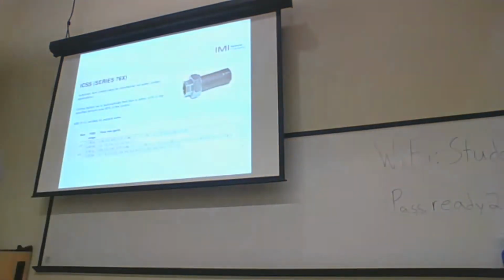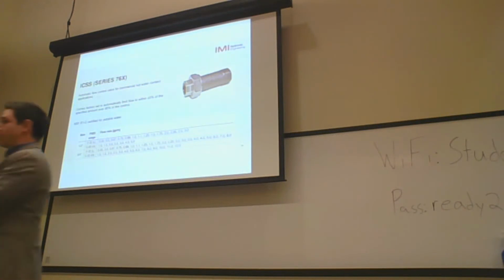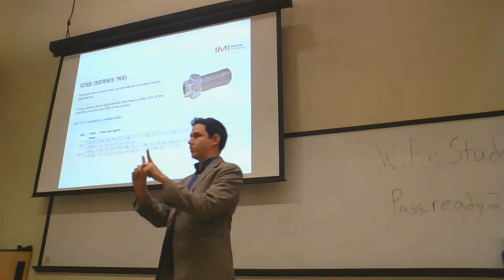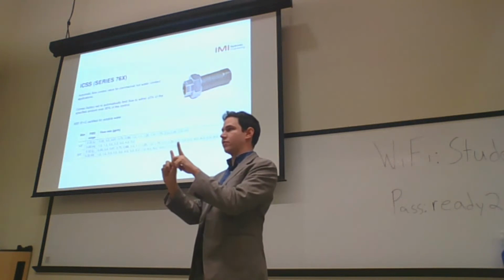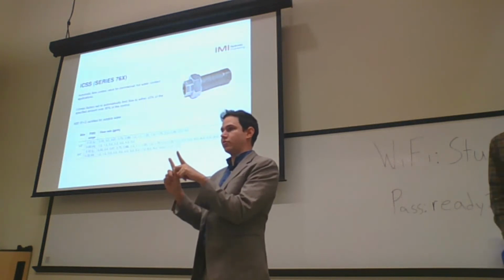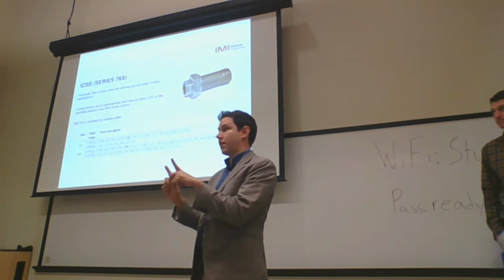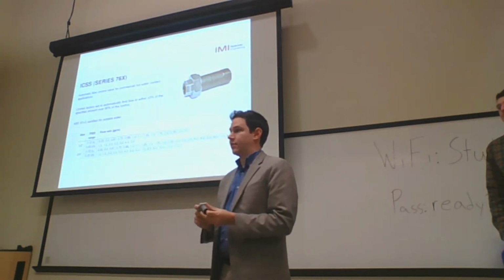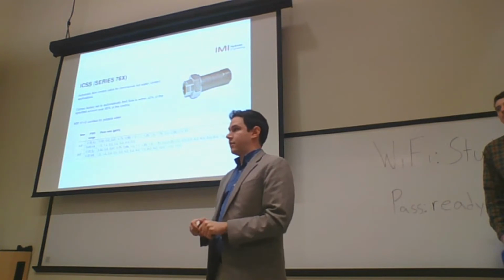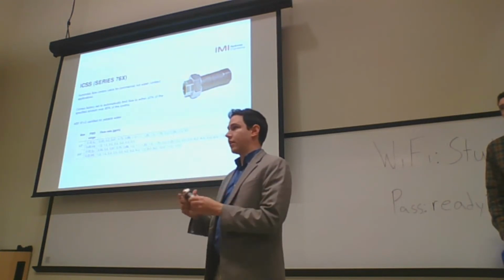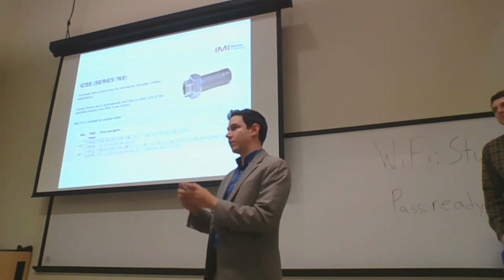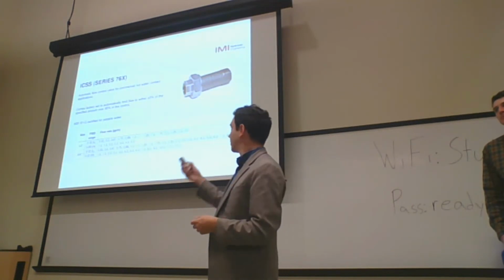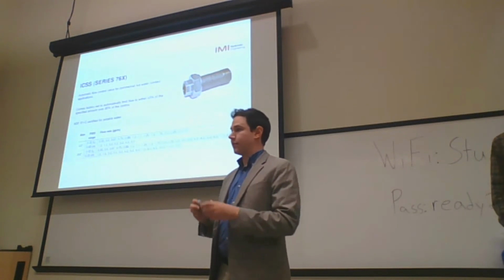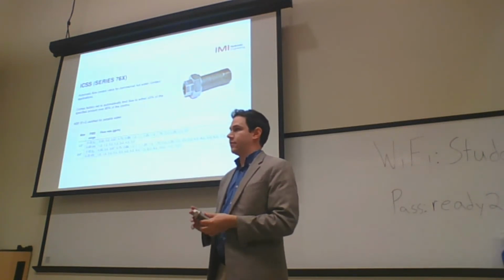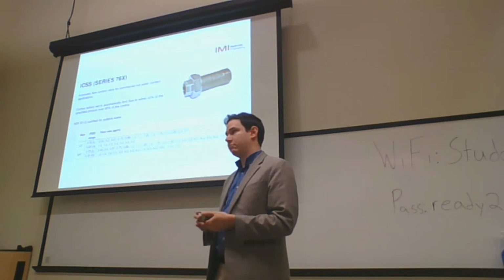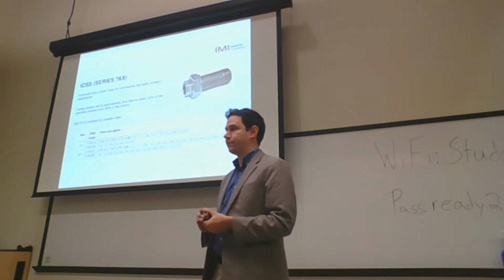An automatic balancing valve, because of this cartridge, is a design of the valve. Even if you put the two PT ports, you never know what the CV of the cartridge is. When you measure the delta P, you're just assuming that you have the right flow rate. The max flow of that valve is rated at some temperature of water while it's running through that, right? Yeah, a big range. The flow rate doesn't matter in that way, but yes. So that's what I'm saying, you would have to measure that valve cold, know what the max flow rate was going through there, knowing that it would be less than that when the temperature increases. Yeah, that could be a good way.